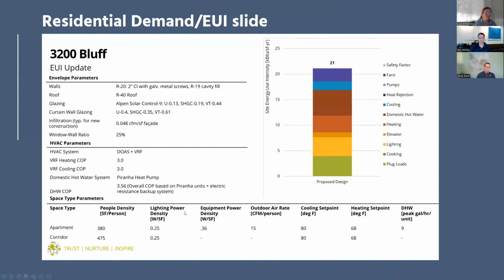Here's an example of a residential pancake chart or bar graph, showing different energy loads that dominate. From the bottom of the blue down is really the difference: we have a much higher domestic water load, shown in that dark maroon or rust color. The heating load is also higher, because in an office building you generate heat from machines and people during the day, but at night when it's colder, generally people aren't there. So office buildings are often cooling-load dominated in our climate, while residential buildings are mostly heating dominated.